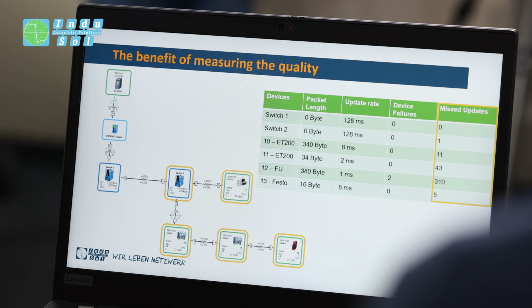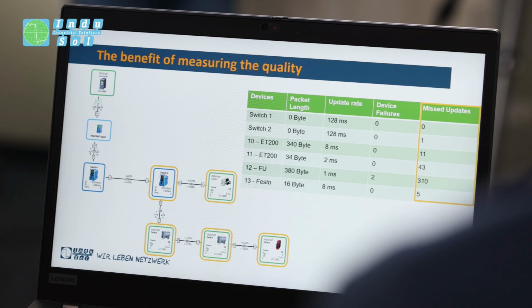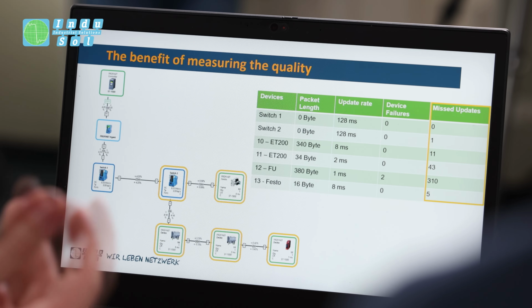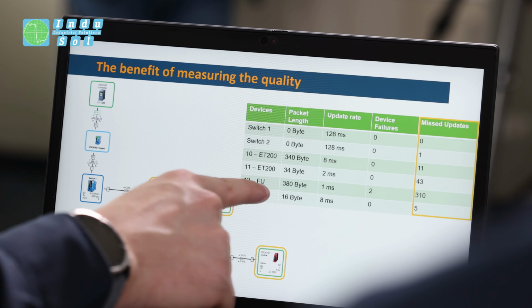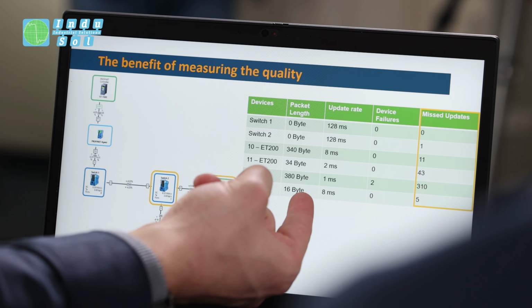So oftentimes the first device that fails is not the root cause of the problem. Exactly, or the root cause is not located at this device. Because often devices are configured differently. You can see it here, for example: device number 12 has the biggest packets, the biggest telegrams, and sends with the fastest update rate. That means you have big packets and a lot of them, so the possibility that a sporadic issue hits such a packet is way higher than for devices with small packets sending way slower.